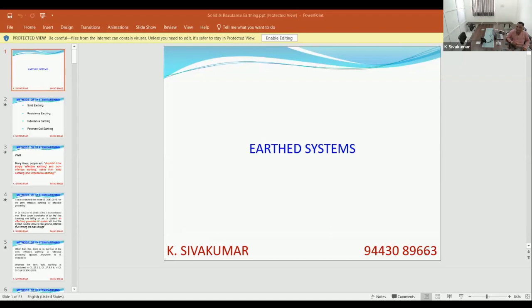and zero sequence impedance. In industrial networks, the resistance is kept very low. Any impedance is R plus jX. Generally the R component is kept very low because that is dissipation of energy. The X component is kept very high because it is utilization of energy. So generally R is negligible. So instead of saying positive sequence impedance, negative sequence impedance, zero sequence impedance, we say positive sequence reactance, negative sequence reactance, and zero sequence reactance.